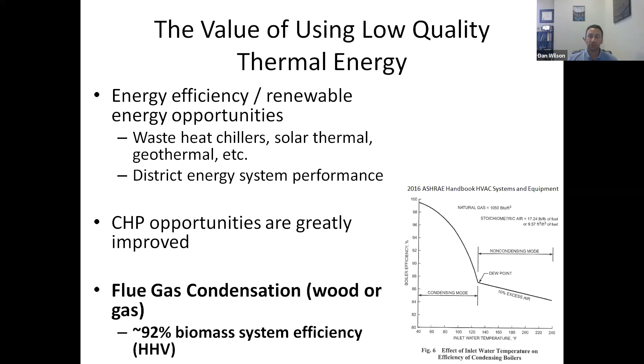District energy becomes a lot easier in terms of its efficiency for piping. And then on the wood side, in addition to the CHP benefits, flue gas condensation is a really great technology where we can condense all the steam and latent energy in the flue gas and capture that heat and use it in the building, if we have a low temperature sink instead of needing steam. We can get up to 92% efficiency on the wood boiler pretty easily if we have a use for that heat. It also helps a little bit with emissions.